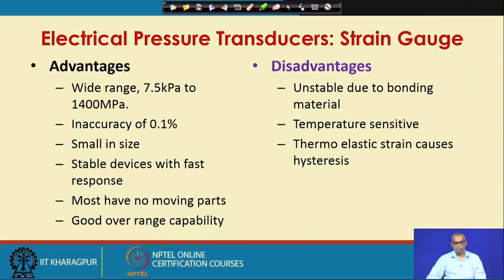There are certain advantages of strain gauges. Advantages are: wide range, 7.5 kilopascal to 1400 megapascals. So, electrical pressure transducers based on strain gauges have a wide range of 7.5 kilopascal to 1400 megapascals, inaccuracy of 0.1%, small in size, stable devices with fast response. Usually they do not have any moving parts, good overrange capability.